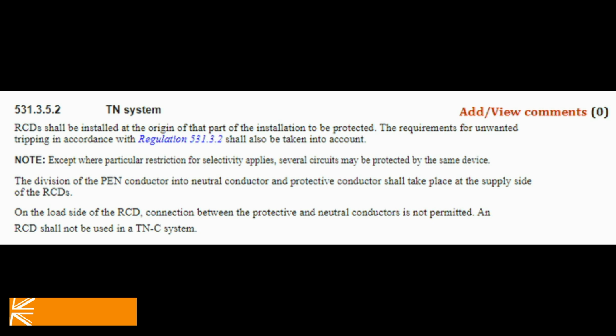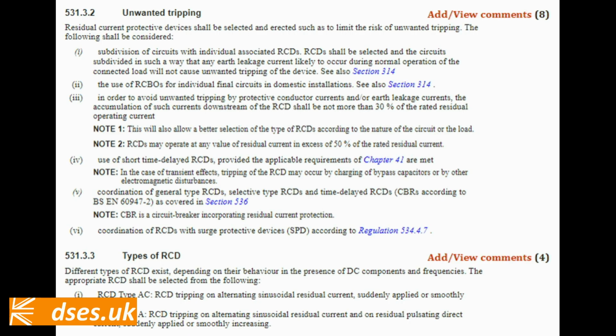Instead, it refers back to 531.3.2, which now proffers the use of RCBOs for the first time. This is a positive move against dual RCD boards and the whole single point of failure problem. The regs are trying to get us to eliminate that from our designs, and about time too. So you're not going to see them now introduce AFDDs in the same way, as that would be telling us to remove one problem while introducing another of exactly the same nature.